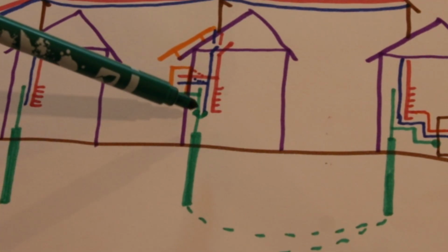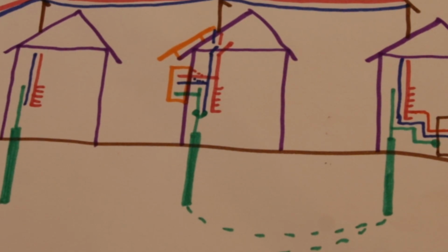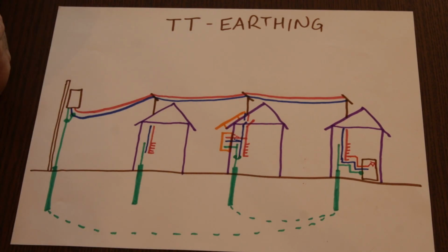You will have currents here. You could now actually also measure currents at your neutral to ground bond, and that would also confuse you, because you would probably think there is some fault in your system. Why would you otherwise have fault currents on your neutral to ground bond? But in reality, that fault current is not yours. Parallel or multiple ground fault loops in this earthing configuration could cause unexpected system behavior, and not just for you, also for other users who are connected to this system.